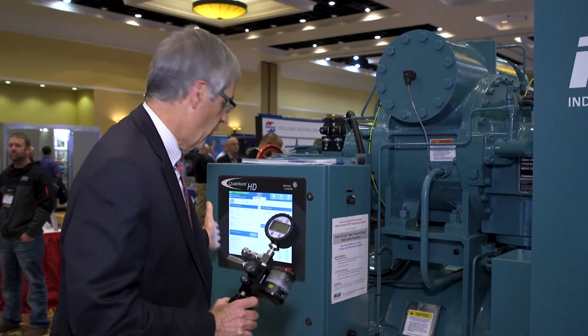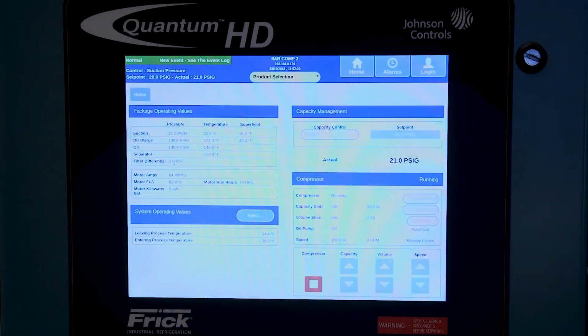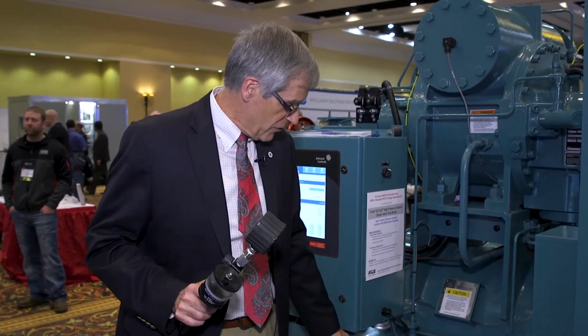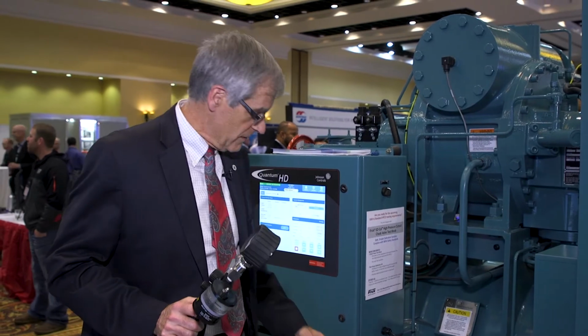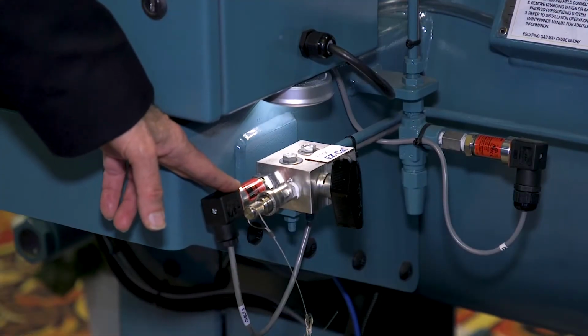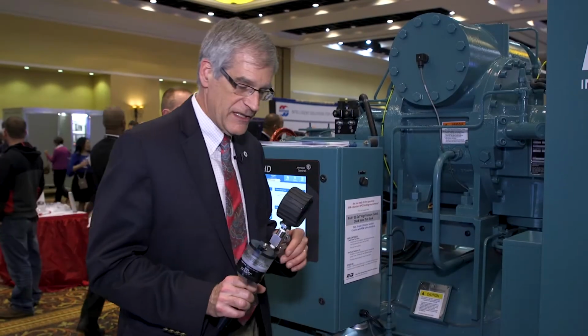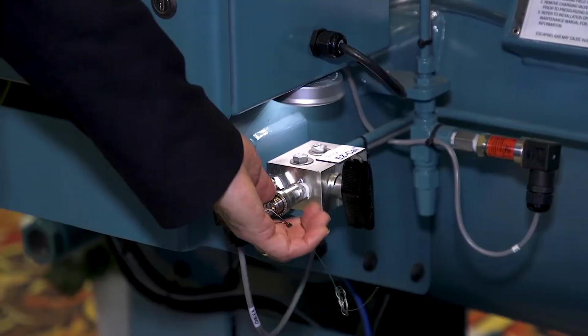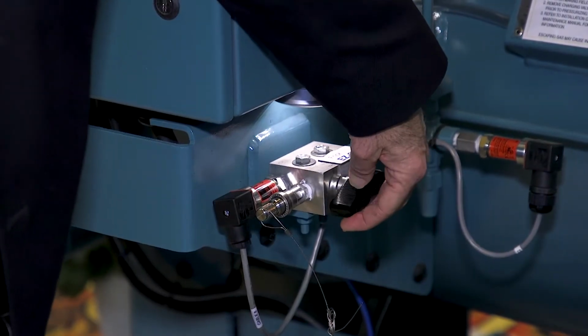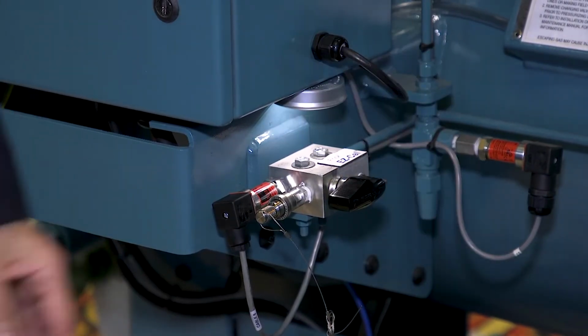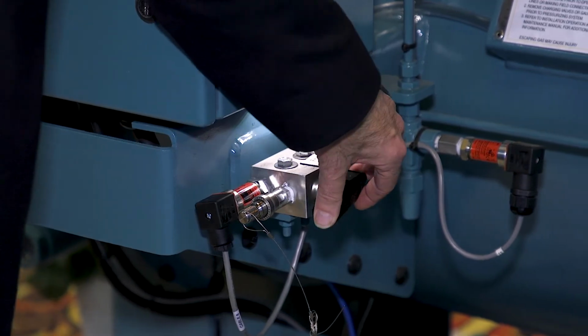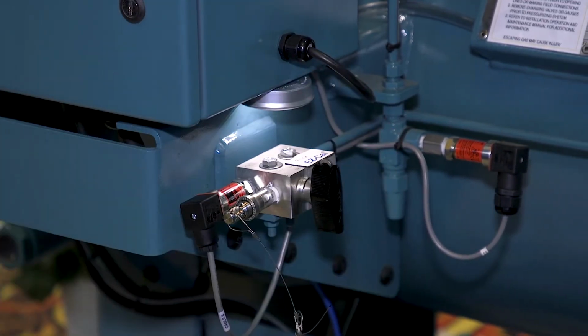So on our package, we have a microprocessor controller, the Quantum HD, and a discharge pressure sensor that is used both to display the discharge pressure and also for the function of the high pressure cutout. And if I'm ready to do the calibration on the block, we will have a switch that allows us to operate in the run position, or when we're going to do a calibration, we'll switch it to the calibrate position.